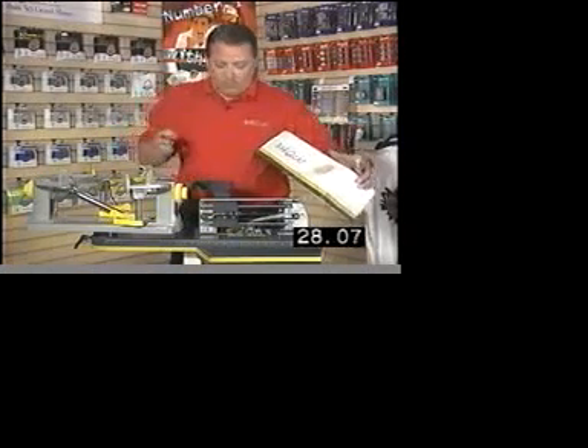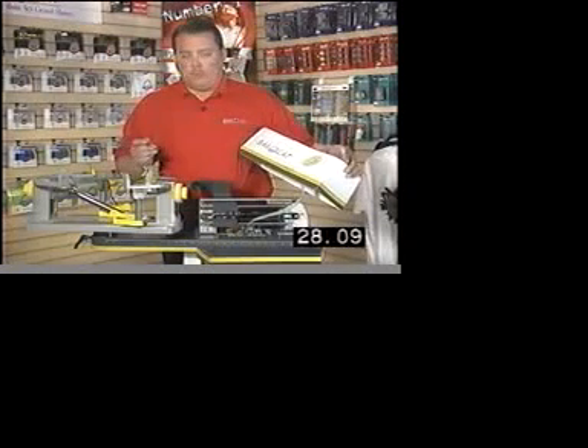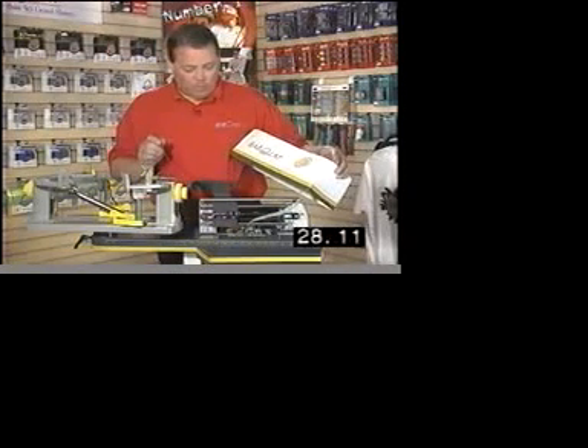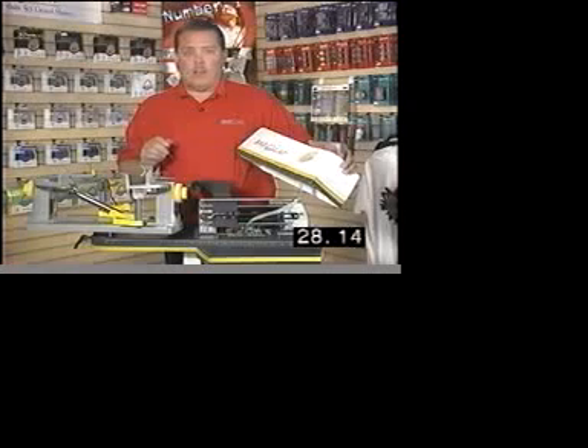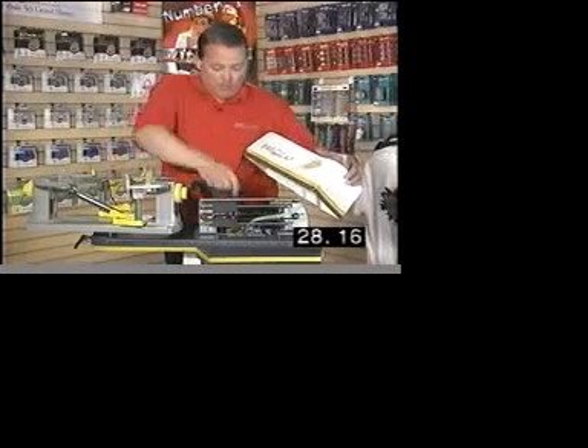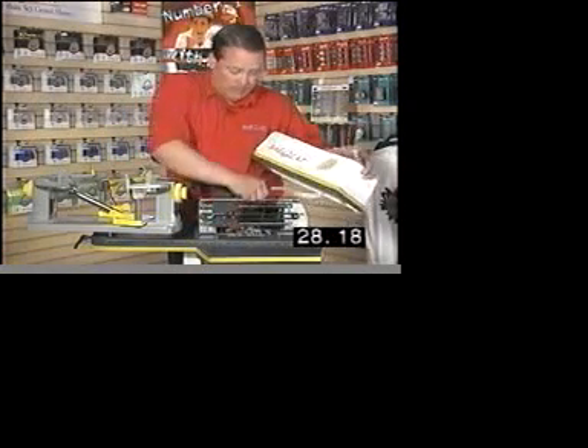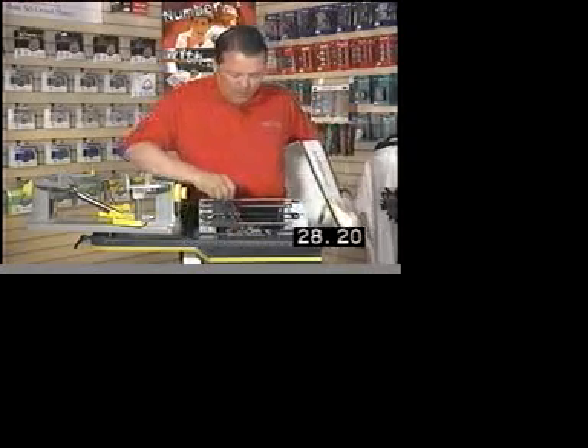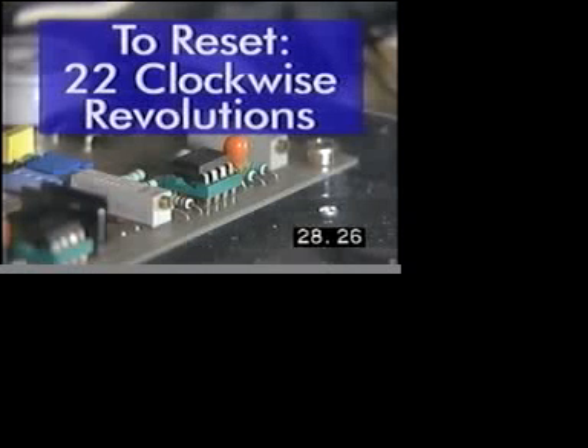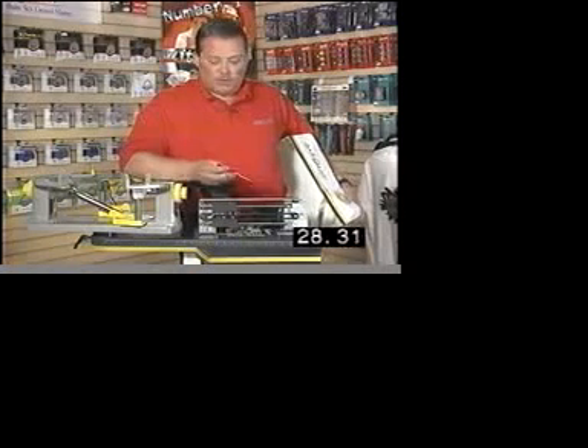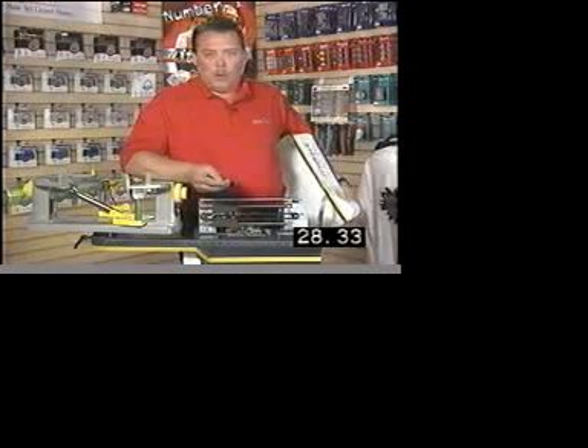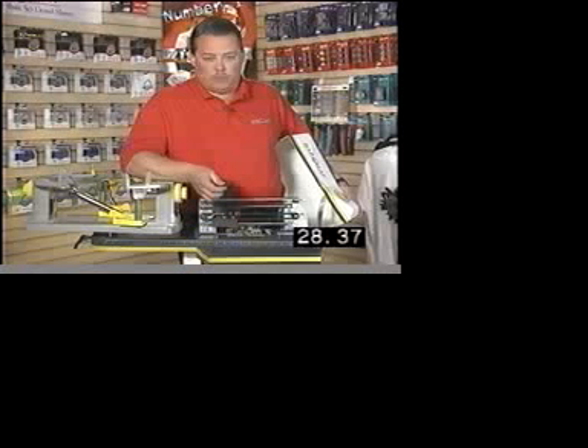If for some strange reason you were off 10 pounds or something like that, what you could do is reset your calibration pots. The way you do a reset is unplug your cover so you can get to it. These calibration pots will turn forever. In order to reset them to the center, you turn them 22 times clockwise. 22 full revolutions. So take your screwdriver and put a mark on one end of it and count that it goes around 22 times in the clockwise direction.